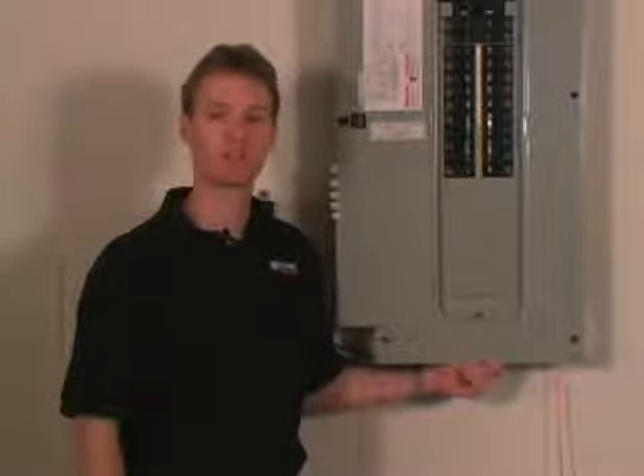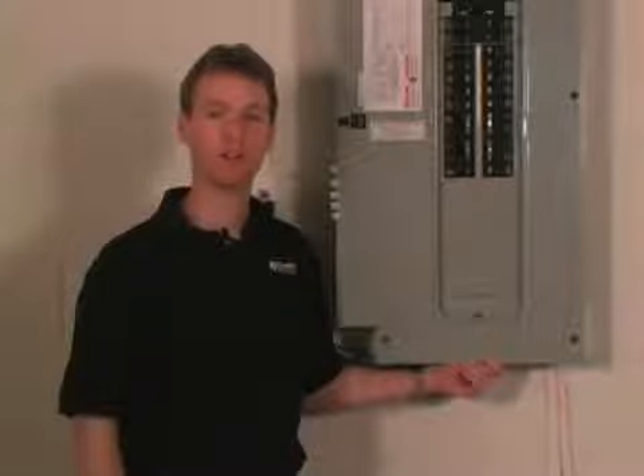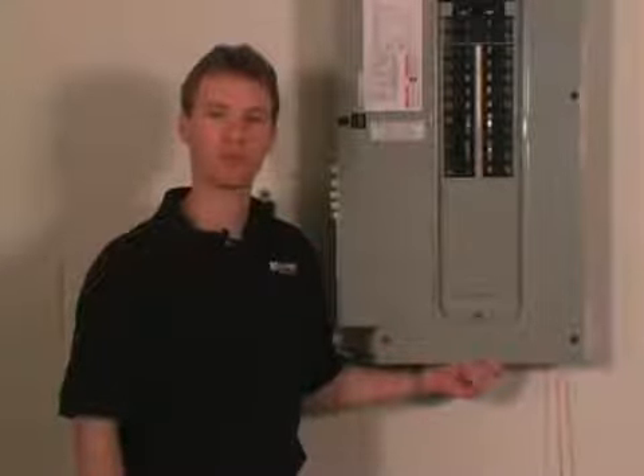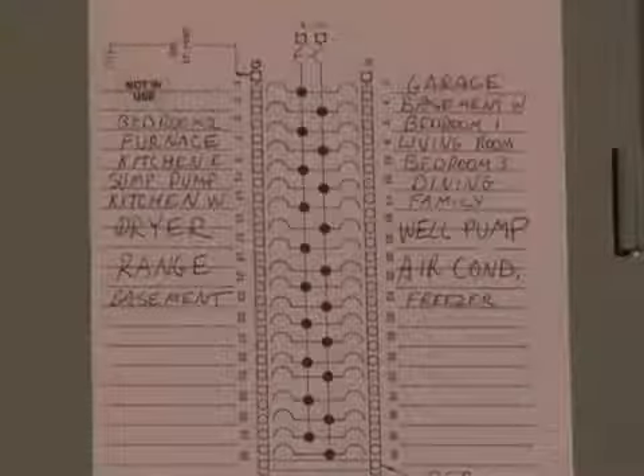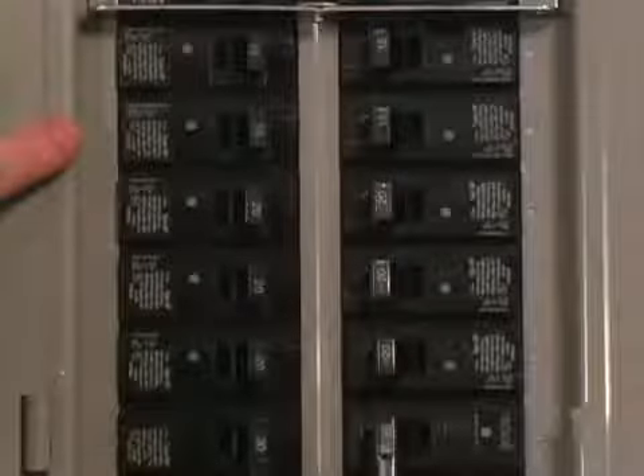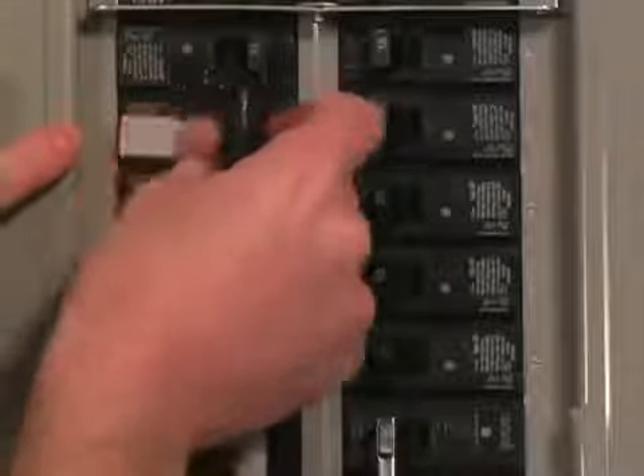I'm going to attach the furnace fan to circuit A, so I'll locate the furnace breaker and mark it with tape. As I look at the load center circuit breaker diagram, I can see that the furnace is on breaker number 7. Now I'll locate breaker number 7 and mark it with the letter A.